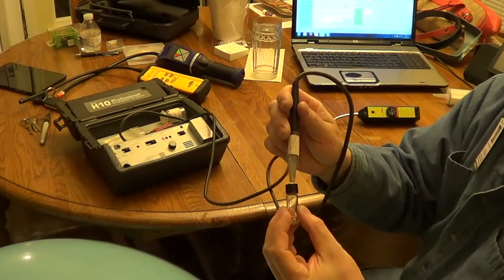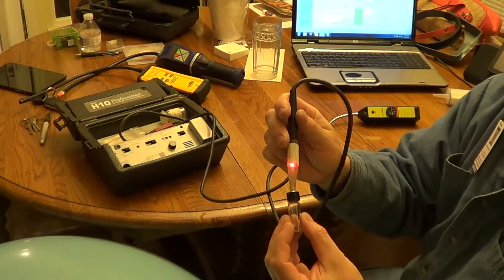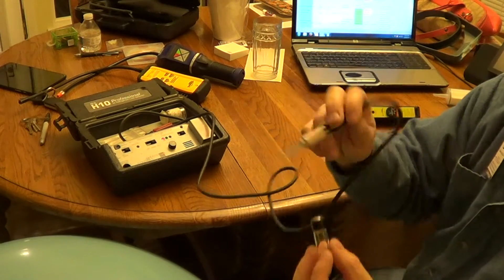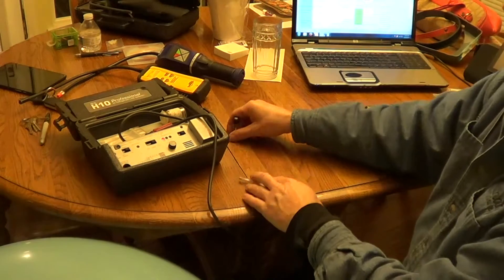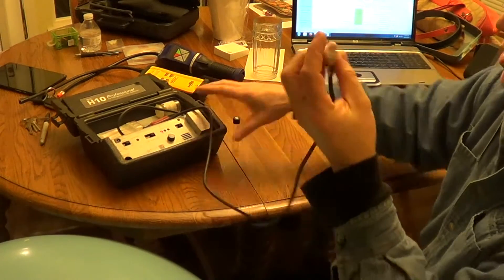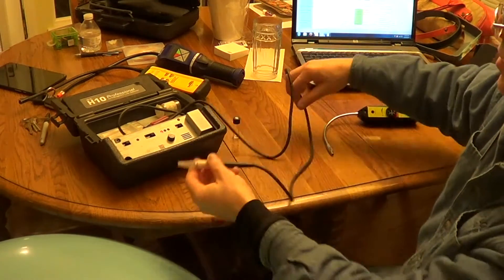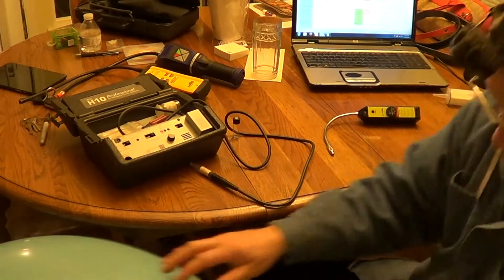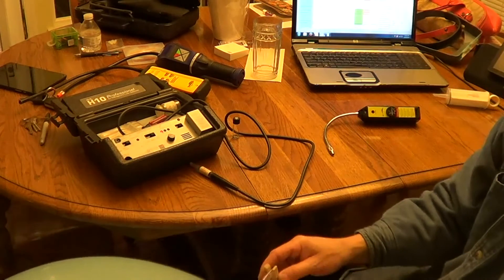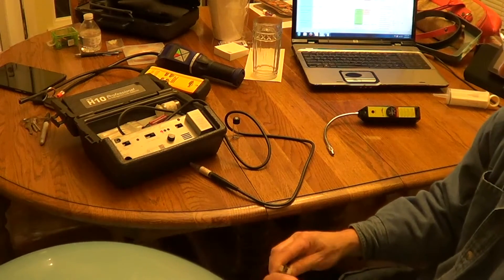You run the sensor. It picks up the reference leak, but it just picks it up really close. But the sensitivity on the R410A is very poor if you set it up like that.